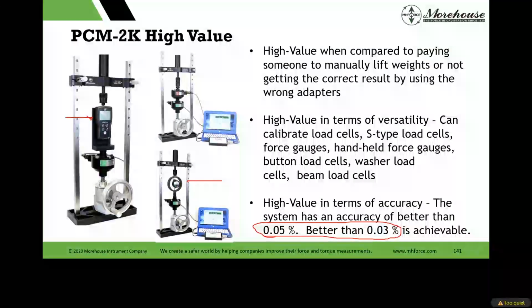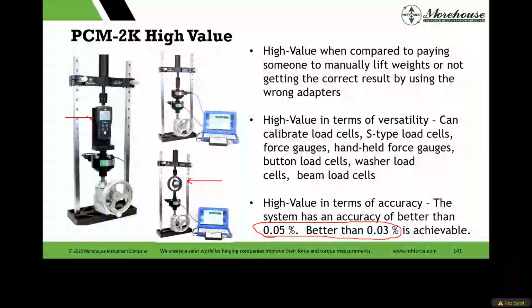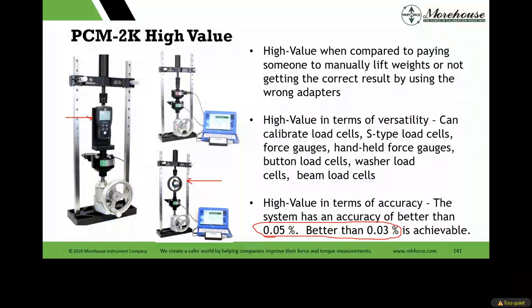These force gauges, some of them are 0.5%, so over 10 times better. Load cell to load cells, you're about something like that. If you're calibrating to the E74 standard, you can do it. It's a little bit more, you're going to have some additional uncertainty with it.